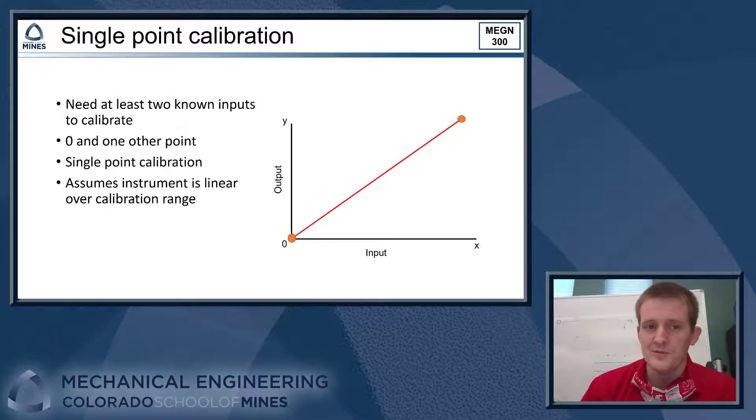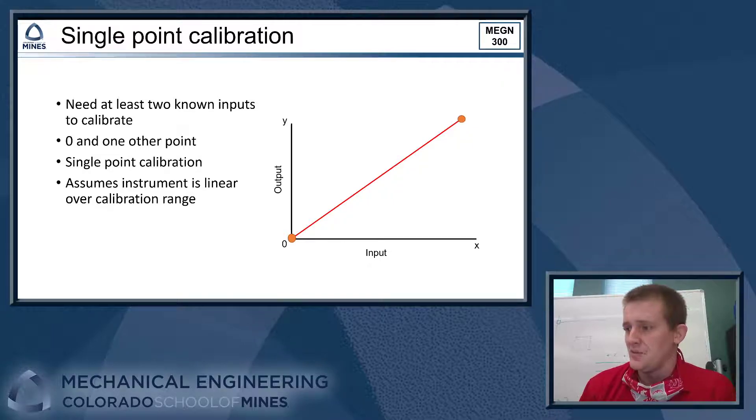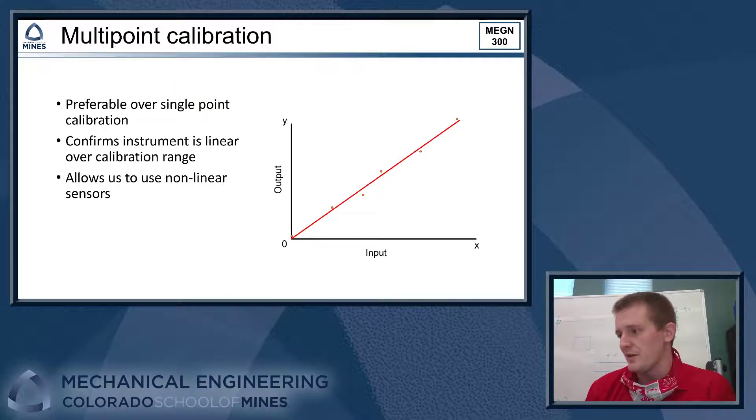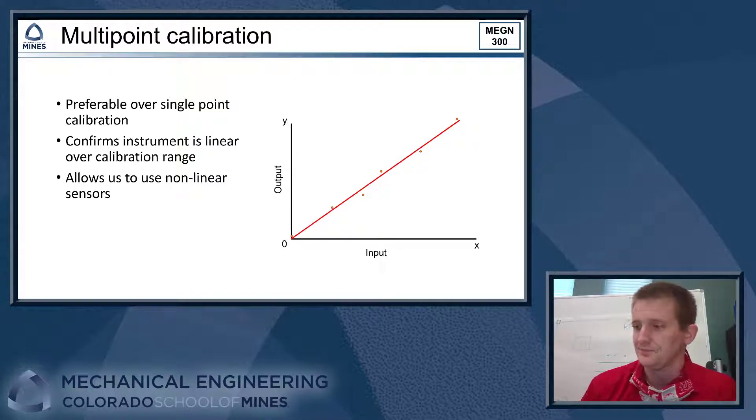All right, so to perform a calibration, we always need at least two points so that we can draw a line between them. We can do what's called a single point calibration where we know zero and then one other point. So we have a single point beside zero, and we use that for our calibration. This assumes that the instrument is linear over the calibration range, which may or may not be a good assumption. So it's always preferable to do a multipoint calibration where we have multiple standards that we apply to our instrument, and we build the calibration curve. This confirms that the instrument was linear over a calibration range if the instrument is in fact linear, but it also allows you to do things like use a nonlinear sensor. So your thermistor is a good example of that where you have this log function that describes how the thermistor works. In that case, we can build that log function by taking a multipoint calibration and fitting data to that multipoint calibration curve. And that allows us to use devices that are nonlinear.